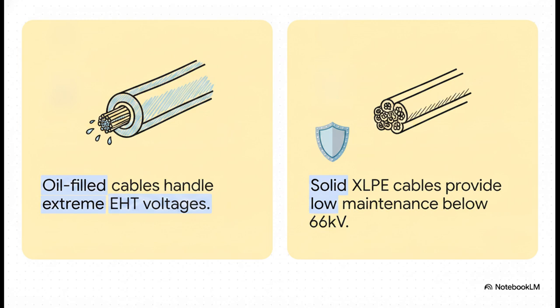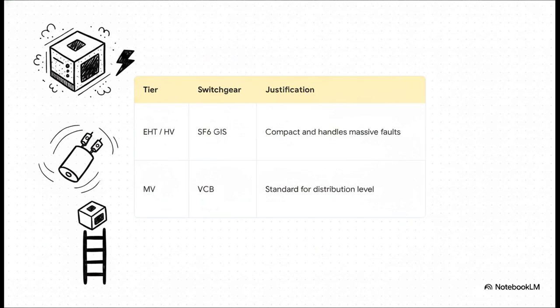It's a very calculated trade-off. You get maximum insulation where you absolutely need it at the highest tiers, and lower maintenance with zero risk of oil leaks at the lower tiers. And you'll find that exact same hardware logic applies at the substation level too. Your voltage classification dictates your hardware. At the EHT and HV levels, where space is at an absolute premium, Singapore relies on gas-insulated switchgear using SF6 gas. It's highly compact and can safely handle massive fault currents. But move down to medium voltage, and the standard shifts to vacuum circuit breakers. Once again, that specific number on the ladder dictates the physical reality of the grid's hardware.